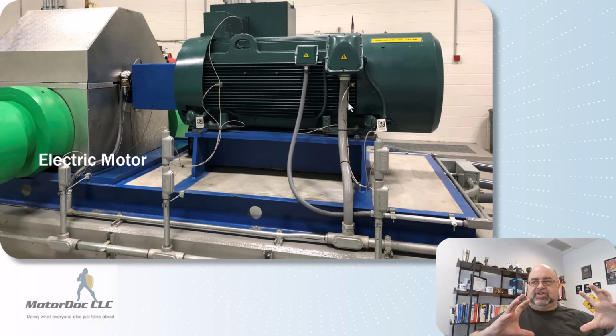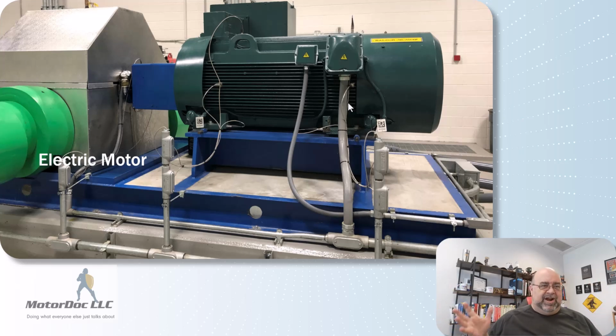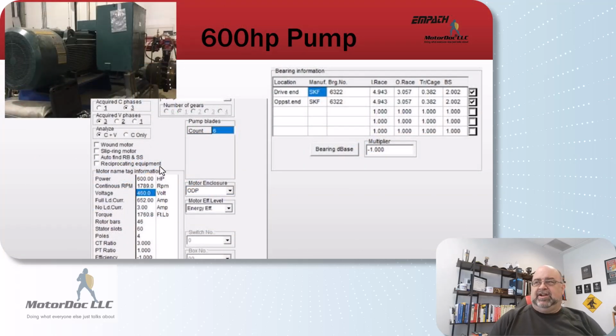But in any case, being able to do work through inverter-driven equipment has been around since the 1990s. This is not something new. It was being incorrectly produced at EPRI as something brand new that required research. Sorry, as a matter of fact, the case studies I had submitted in my paper for EPRI were all inverter-based systems. So this is a 600 horsepower, 460 volt machine, as you can see here. This is the 6322 bearings that are on both ends of this machine. There's also some pump bearings in there. Didn't have them because we're not focused on that for this case study.